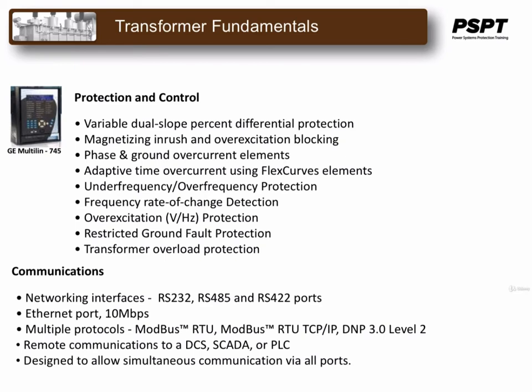This relay, as well as most modern IEDs, comes with communication capabilities that include network interfacing, RS-232, RS-485, and RS-422 ports. It has an Ethernet port for sample rates up to 10 megabits per second. It uses multiple protocols: Modbus RTU, Modbus TCP/IP, DNP, and several others, for remote communications to a DCS, SCADA, or PLC type system. And it's designed to allow simultaneous communication via all ports.